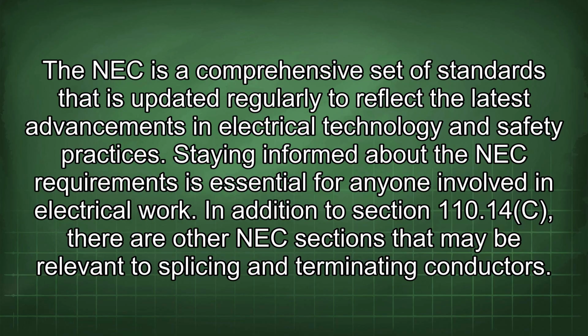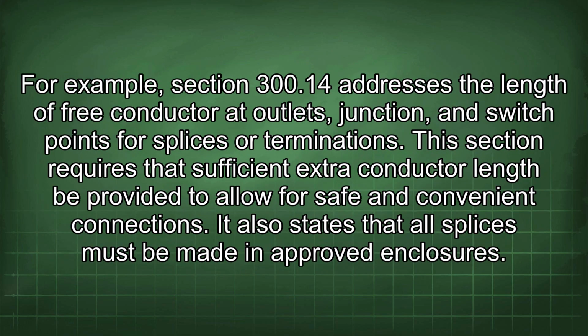In addition to Section 110.14(C), there are other NEC sections that may be relevant to splicing and terminating conductors. For example, Section 300.14 addresses the length of free conductor at outlets, junction, and switch points for splices or terminations. This section requires that sufficient extra conductor length be provided to allow for safe and convenient connections. It also states that all splices must be made in approved enclosures.